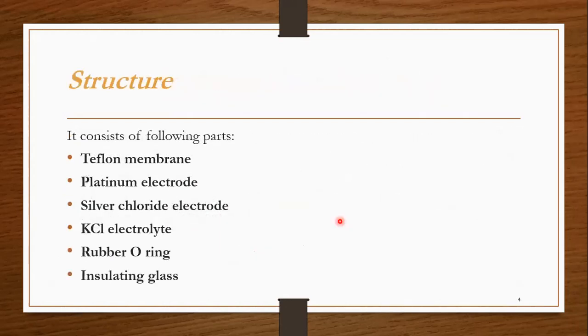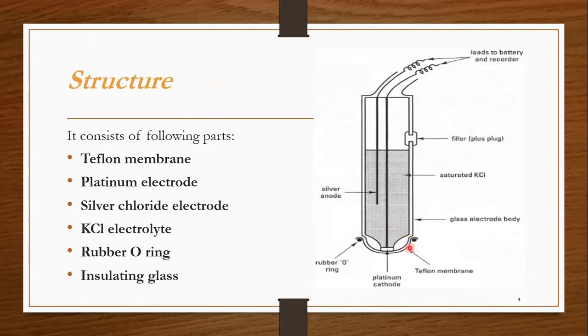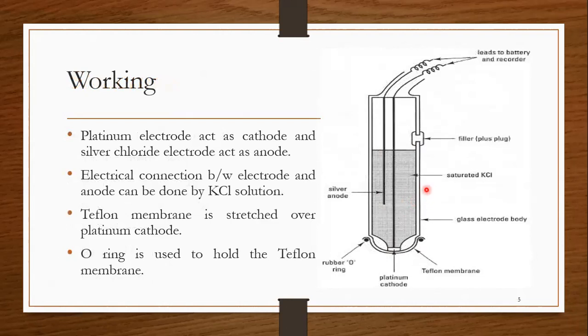Now I tell you about its structure. It consists of a Teflon membrane, platinum electrode, silver electrode, KCl solution, which is an electrolyte, O rings, and insulated glass. Now I tell you about its working.